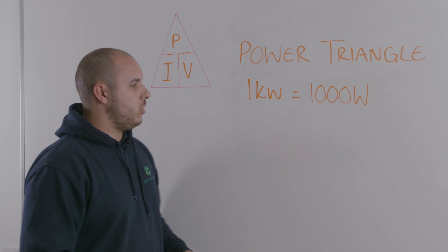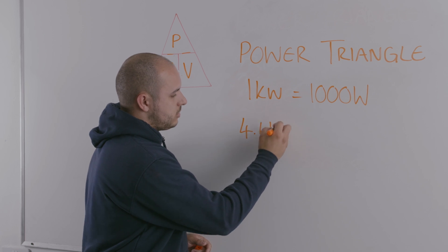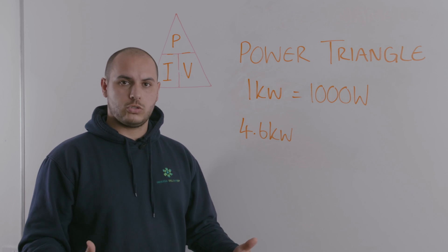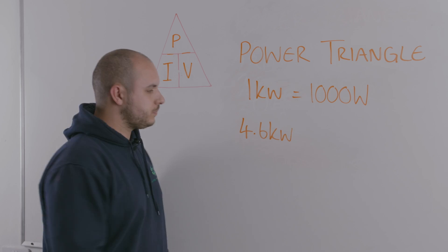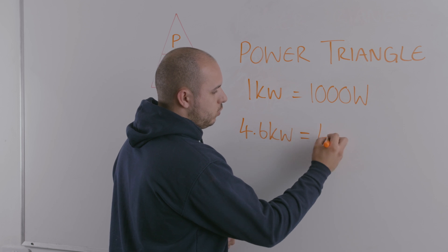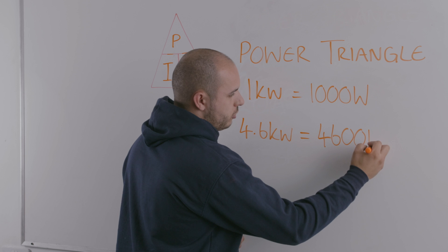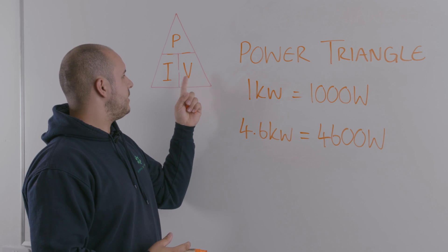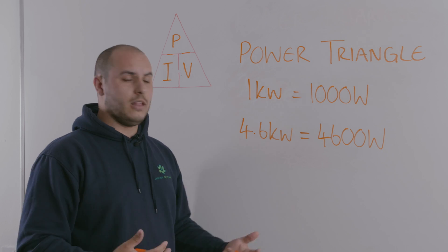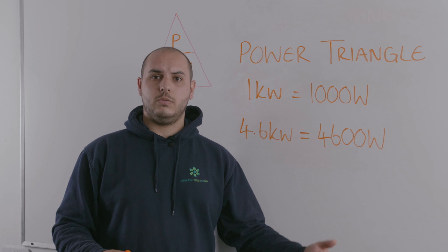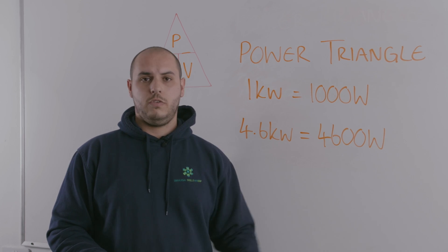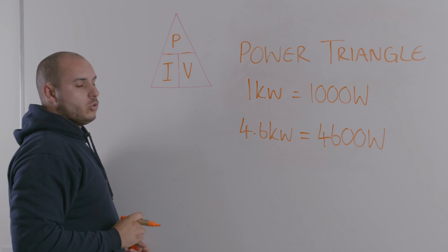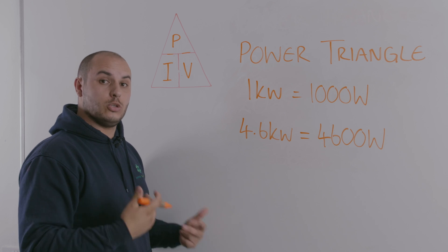For this scenario, we're going to look at a 4.6 kilowatt — say that's an oven or something like that. So 4.6 kilowatts: we need to convert that into watts before we put it into the triangle. So 4.6 kilowatts into watts would be 4,600 watts. What we're trying to achieve here is to find out what the current for that circuit is. If we put our 4,600 watts into the top and we know our nominal voltage used for our calculations is going to be 230 volts.